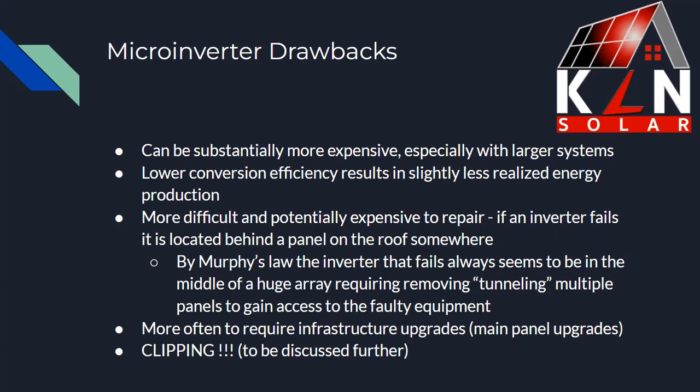Microinverters are more difficult and potentially expensive to repair if the inverter fails, because the inverter is located behind a panel on the roof. By Murphy's law, it never seems to be the panel on the outside of an array — usually it's one in the middle, three or four rows in on some huge array, and you'd have to remove panels to get to the one with the fault. Also, you're more likely to require infrastructure upgrades such as main panel upgrades. And microinverters are prone to something called clipping, which we'll talk about in a bit.